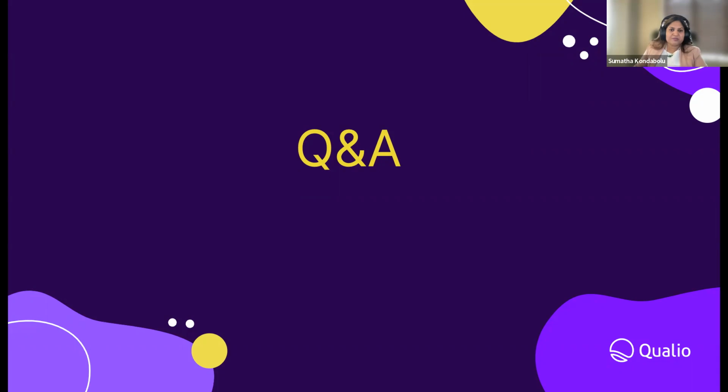And maybe Andrew, would you like to add a few points here? Yeah, so assuming this is for UK, UKCA marking as well. Broadly speaking, there's a lot of similarities with the two. So you likely have done a lot of the work. Technical file is probably largely the same. Again, to some of my points before about notified bodies and approved bodies, if you have a CE mark that needed a notified body to obtain, but that notified body doesn't also offer UK approved body services, you may need to take that to a UK approved body. Sometimes they can review the certification that you've had from the CE marking notified body and do a quick review, but sometimes it may be more of a review from scratch. So the large difference is going to be due to any notified body or approved body reviews. Yeah, a lot of overlap as well.